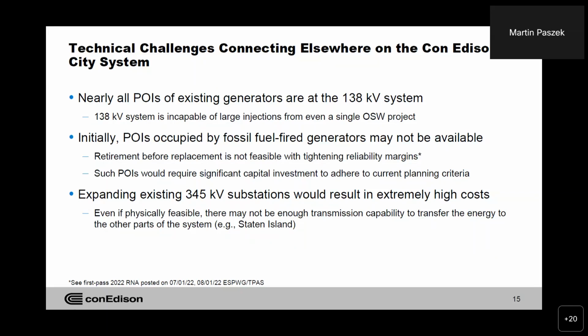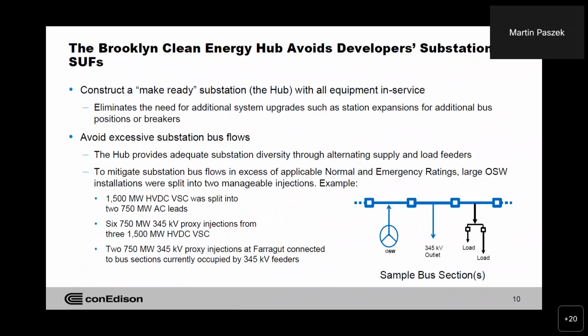That was one question. There was also a question on slide 10, if we can go back to it. The question was, if there's time, can we talk through again how alternating offshore wind 345 kV outlet and load improves diversity? As Deidre described, the station is really designed in a manner to avoid excessive substation bus flows, really to eliminate overloads within the station. And this is the key, this is within the station, not on the transmission system. On a very high level, an injection at one bus section is really removed at the next bus section if you alternate supply and load. So if you do that, then you eliminate power flow through the station, as compared to having two injections on two adjacent bus sections, where there will be additive, creating excessive bus flows. So I hope that I did address that question.